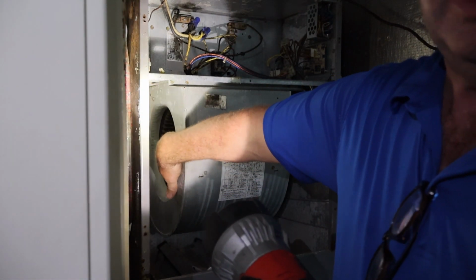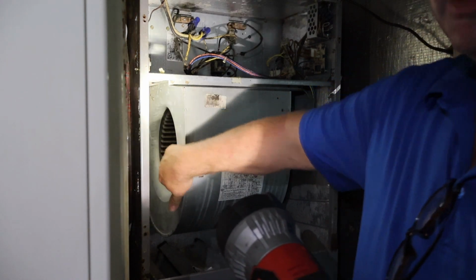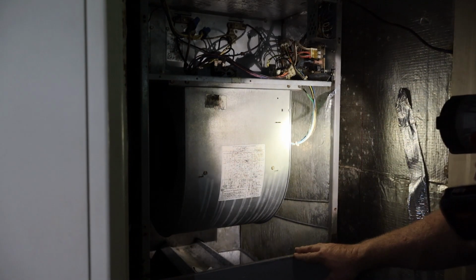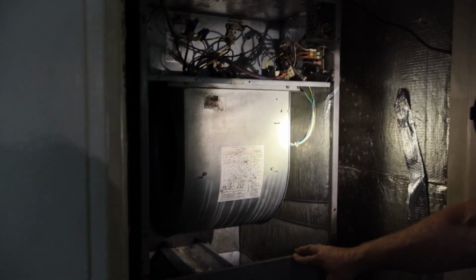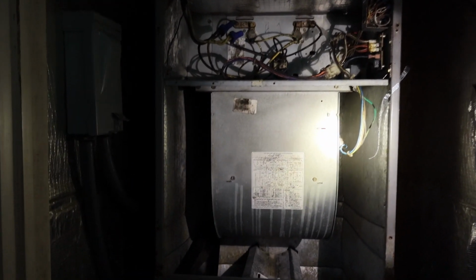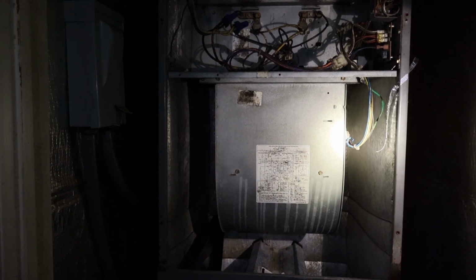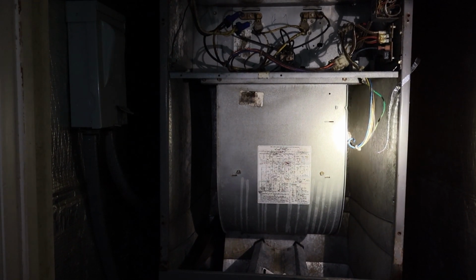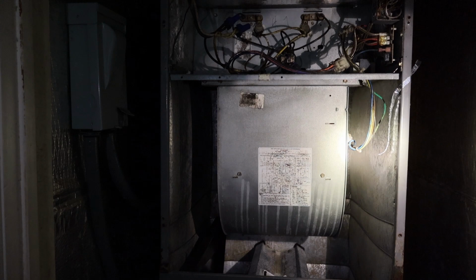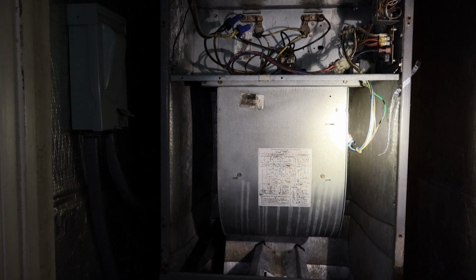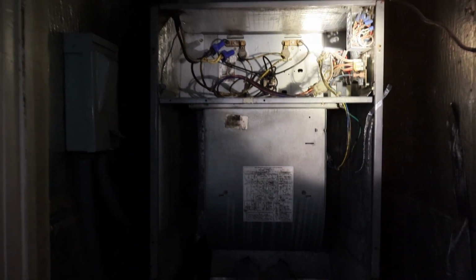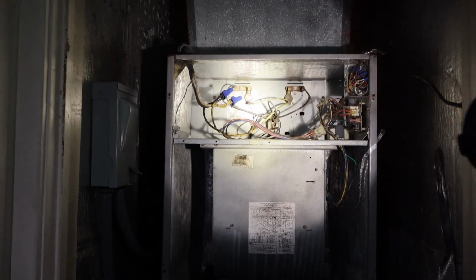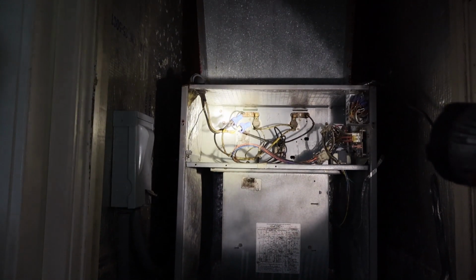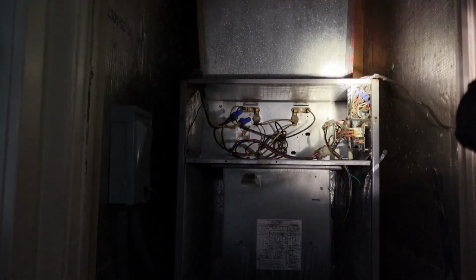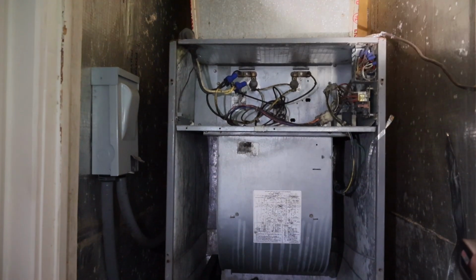You can check the bearings just by the side-by-side play, but the module is right there on this other side. This one looks to maybe be the original, so it's been a good one. But not a whole lot to check. It doesn't have capacitors or anything. Just look for connections. Make sure you've got good connections, nothing burnt on the line voltage wire nuts there, things of that nature. What you can see of the ductwork, which is not a whole lot.